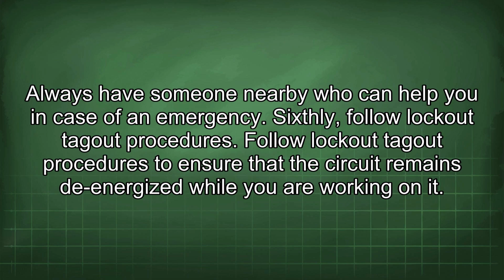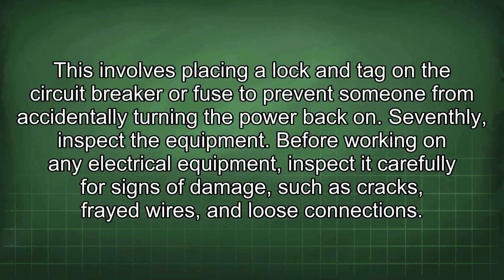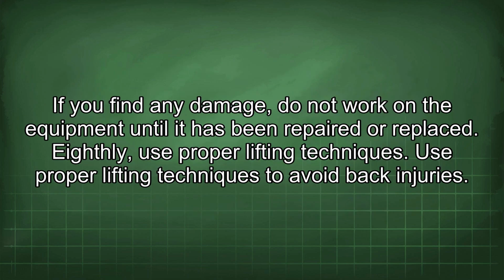Sixthly, follow lockout-tagout procedures. Follow lockout-tagout procedures to ensure that the circuit remains de-energized while you are working on it. This involves placing a lock and tag on the circuit breaker or fuse to prevent someone from accidentally turning the power back on. Seventhly, inspect the equipment. Before working on any electrical equipment, inspect it carefully for signs of damage, such as cracks, frayed wires, and loose connections. If you find any damage, do not work on the equipment until it has been repaired or replaced.